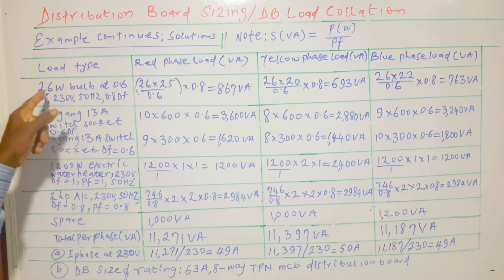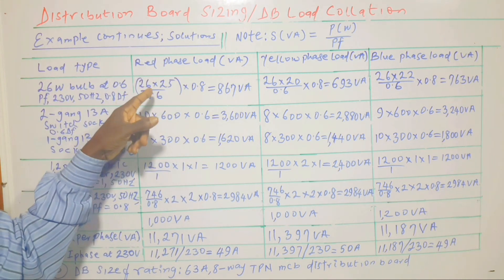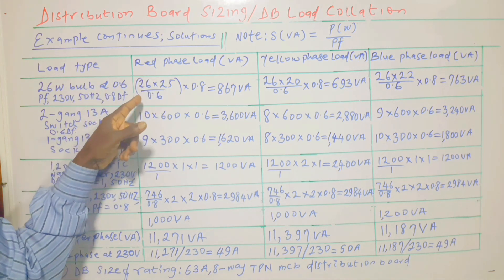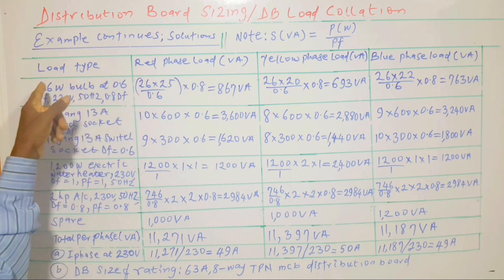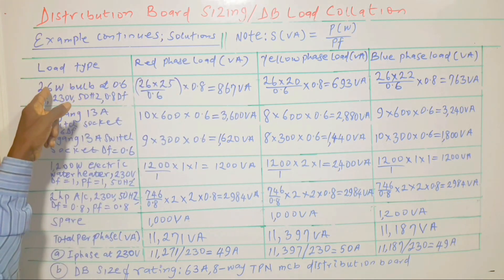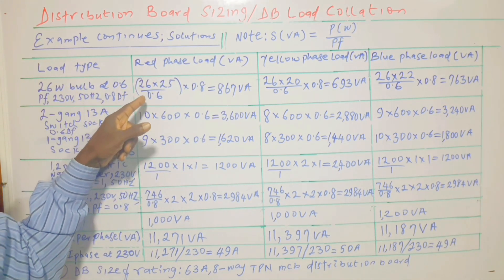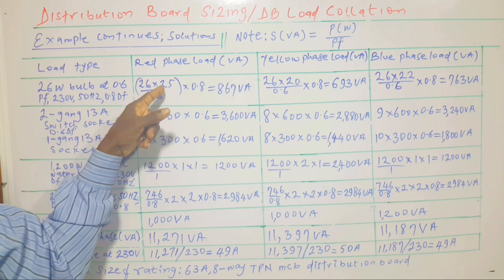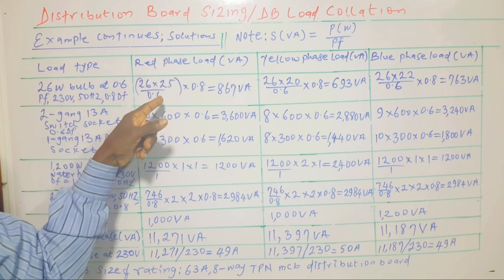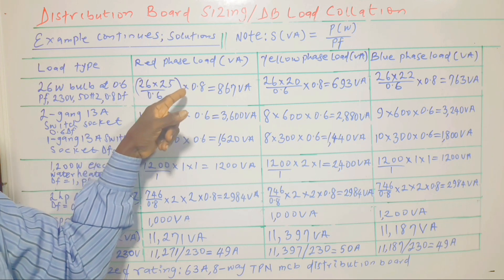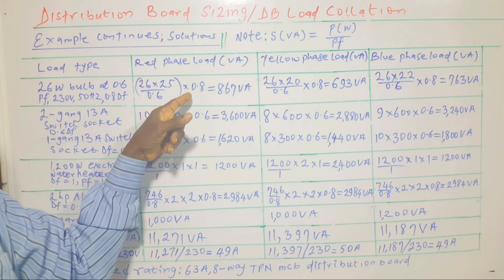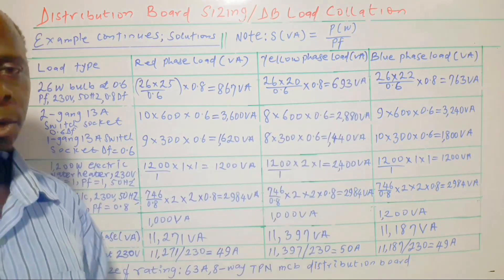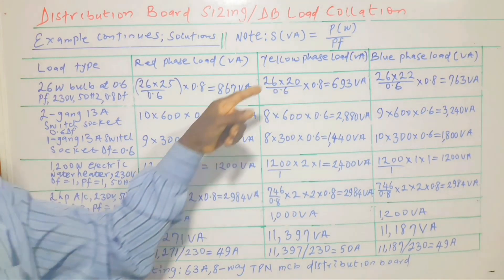For instance, the bulbs: on the red phase we have 25 bulbs, each rated 26 watts. So what is important is to convert 26 watts to VA — divide 26 watts by the power factor — and that gives us the VA, which is then multiplied by the number of electric bulbs on the red phase. Then we multiply the result by 0.8, which is the diversity factor. The same thing holds for electric bulbs on other phases.